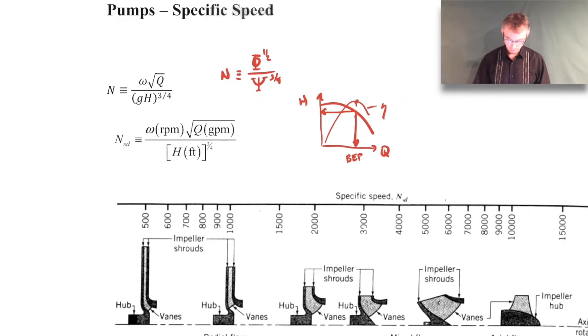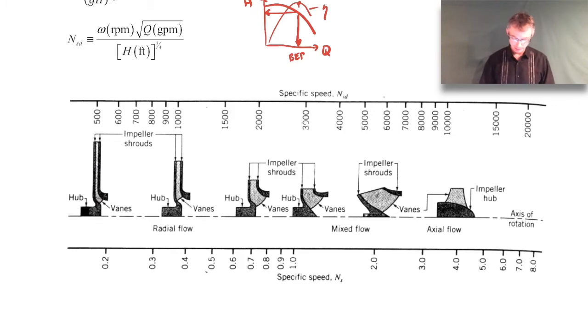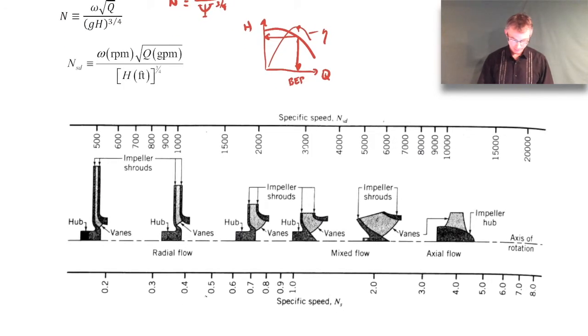And when you look at this for lots of different pumps and kind of categorized based on that, you'll get a plot that looks something like this. So this is a plot showing the specific speeds. So a specific speed down here, the one on the bottom here is using that formula. And then you'll see the different pump types or impeller types up here on the top. So over on the high specific speed side, you have axial flow kinds of pumps or impellers. And then at lower specific speeds, you have radial flow, more like the centrifugal style pumps here. And then in between, you have mixed flow. Here you can see, for example, there's a kind of a combination of axial and radial components to that kind of mixed flow pump.